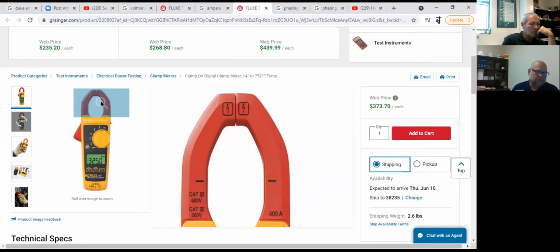Especially if you go into a pad mount transformer, that means like on the far end of our yard, there's all those green boxes. Those can become tightly packed with conductors. You're trying to get an amp reading on a certain conductor in there and you're having to pull wires, so you just want to make sure you get it on the right wire. Make sure you have the jaws firmly closed, because what it's doing is picking up the magnetic field around those conductors, and it's going to show you how much current is flowing through that wire going to that customer's home or whatever it's serving.